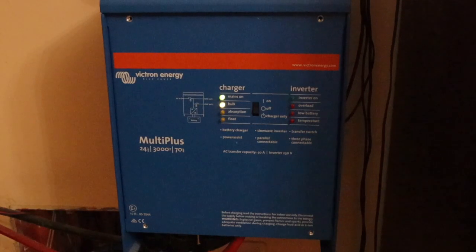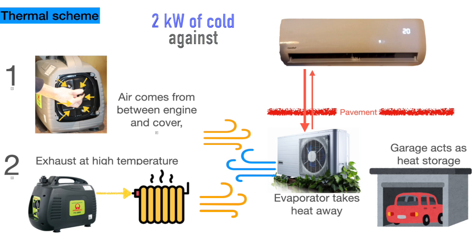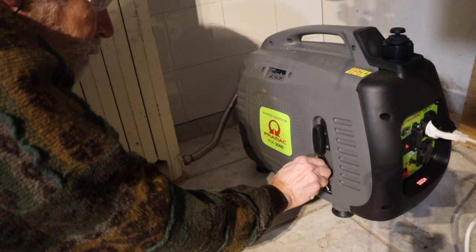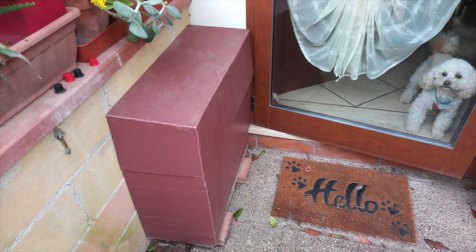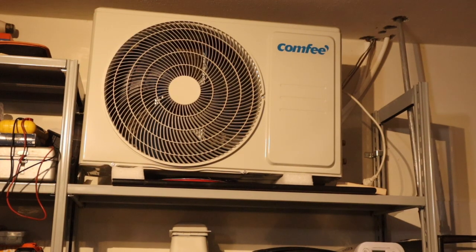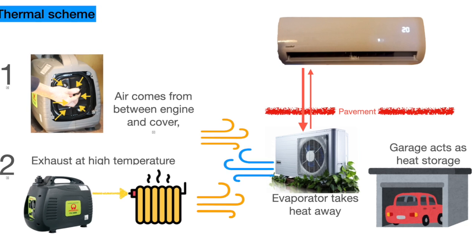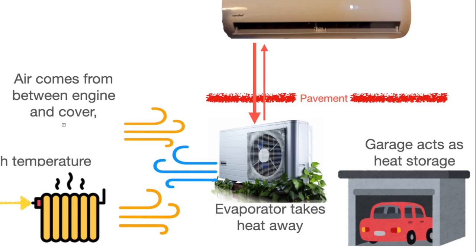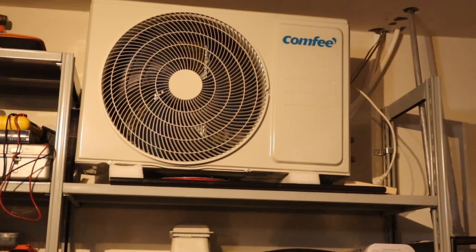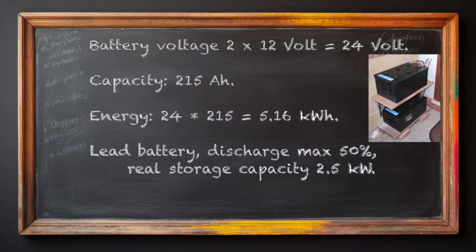When the battery is getting full, it will automatically get less power and allow more capacity for other consumers. From the thermal viewpoint, the heat from the generator is about the same as what the heat pump is taking from the garage. If you switch off the generator for the whole night, the full batteries have enough energy for a load of 250 W — at least with our batteries. Moreover, the heat pump can continue to extract heat from the garage, which will simply cool down a few degrees. The system COP, or coefficient of performance, is more or less 5 due to the small temperature difference between garage and living room, and it doesn't even make condensed water at the usual 15 degrees Celsius.